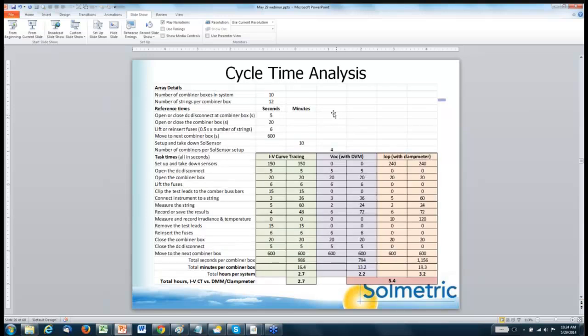The final thing I want to do on the time advantage point is compare a cycle time analysis of IV curve tracing with measuring open circuit voltage using a digital voltmeter or multimeter, and then returning when the array is operating to measure the operating currents with a clamp meter.